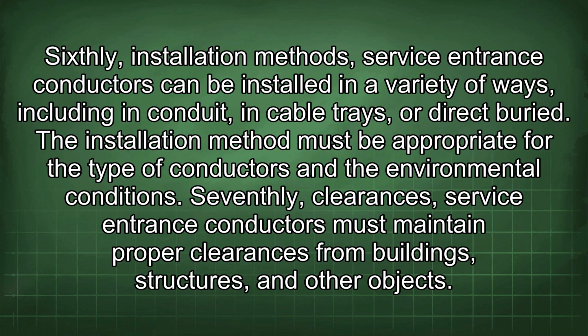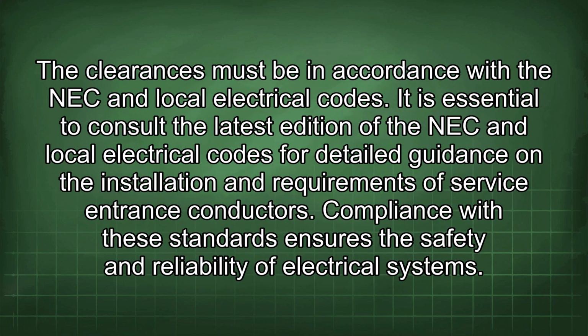Sixthly, installation methods. Service entrance conductors can be installed in a variety of ways, including in conduit, in cable trays, or direct buried. The installation method must be appropriate for the type of conductors and the environmental conditions. Seventhly, clearances. Service entrance conductors must maintain proper clearances from buildings, structures, and other objects. The clearances must be in accordance with the NEC and local electrical codes. It is essential to consult the latest edition of the NEC and local electrical codes for detailed guidance on the installation and requirements of service entrance conductors. Compliance with these standards ensures the safety and reliability of electrical systems.